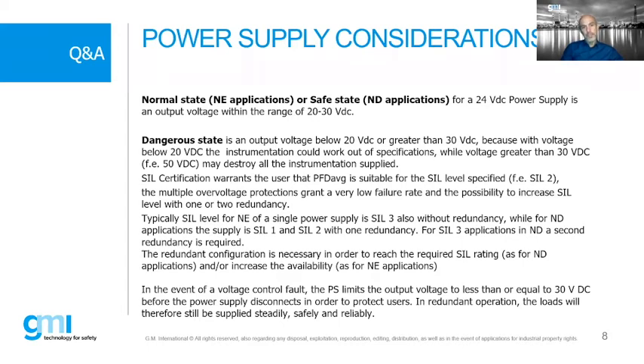So the certification grants that the probability of failure on demand, PFD, is suitable for the SIL level specified, so if you have SIL2 or SIL3, for instance. In this case, multiple voltage protections can grant a very low failure rate. This can increase the SIL level or the availability also, but we are talking about SIL because safety is SIL. Availability is not taken into account in that calculation. So the SIL is increased by 1 or 2 redundancy.